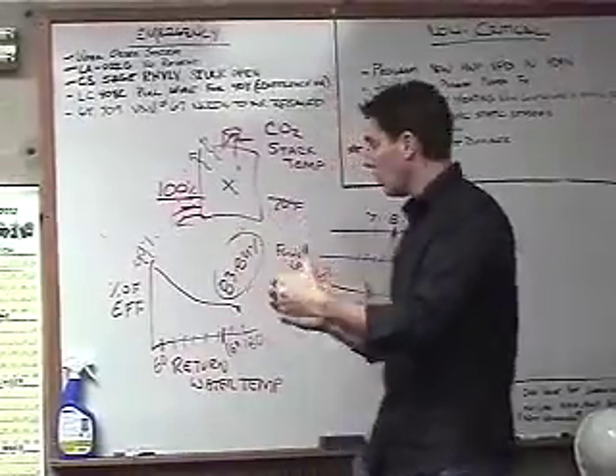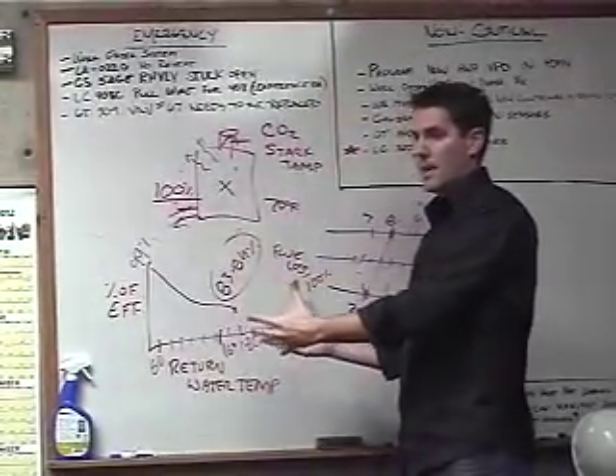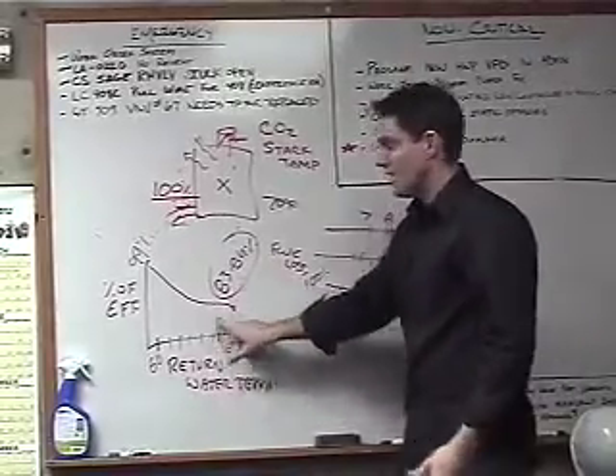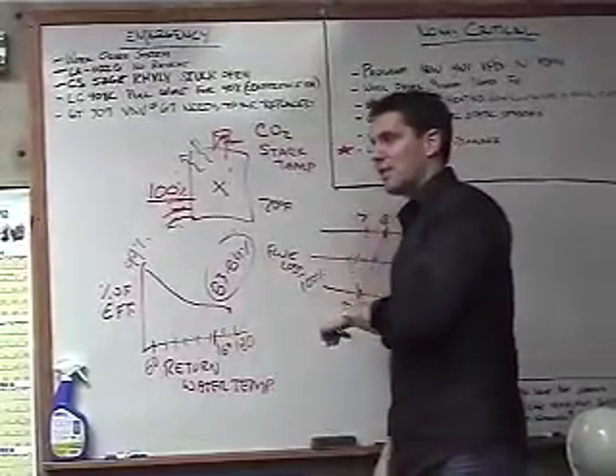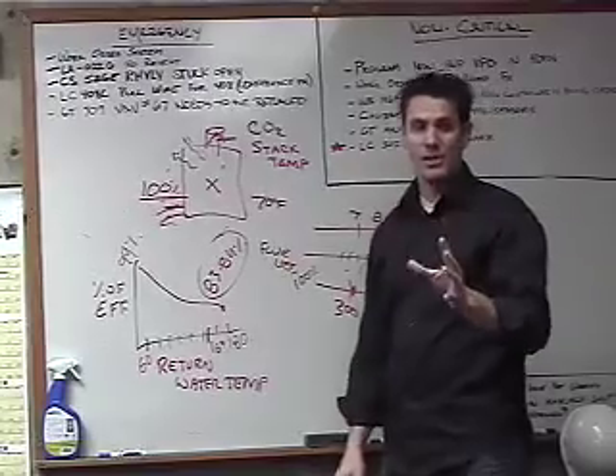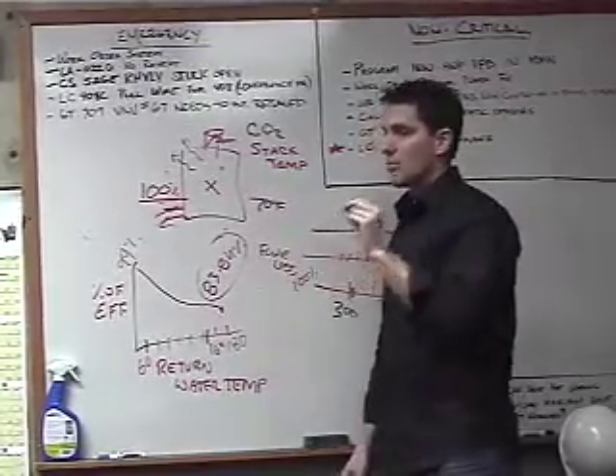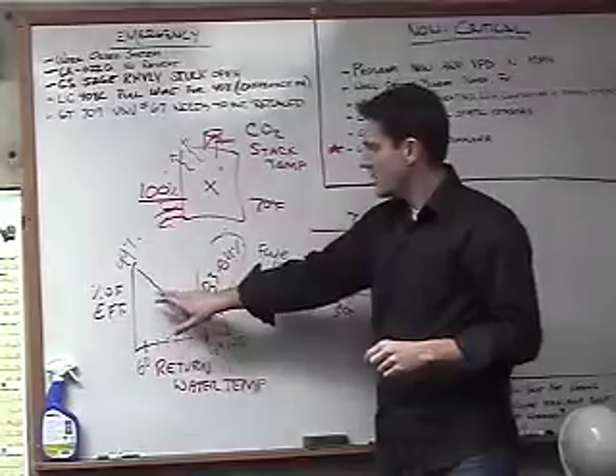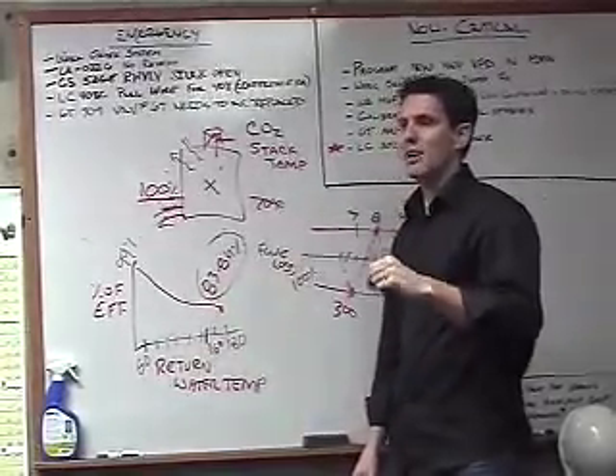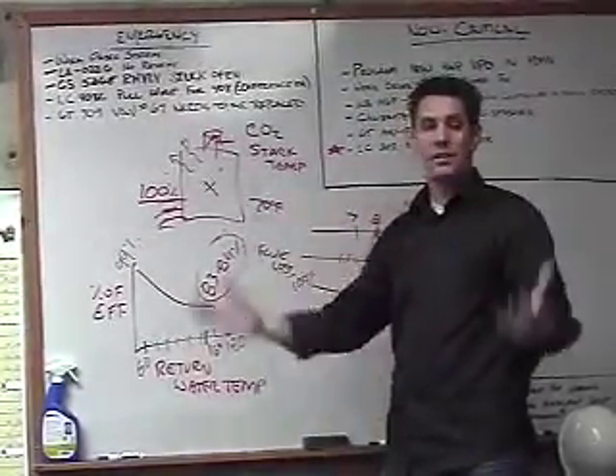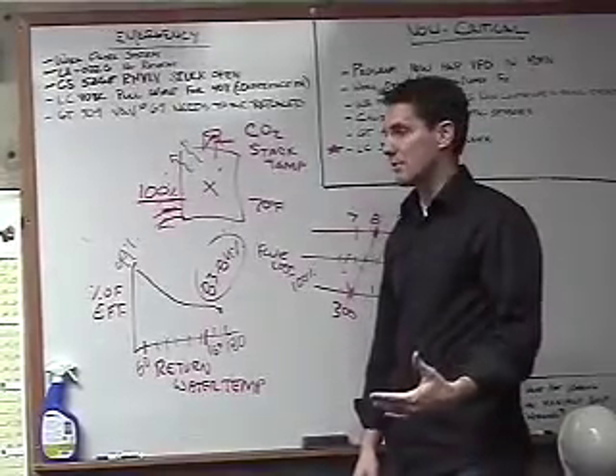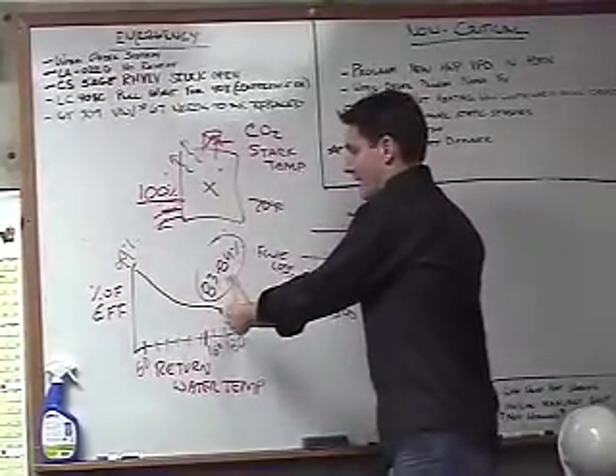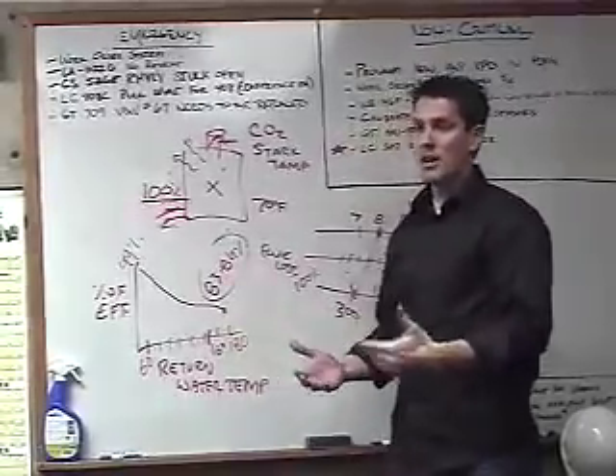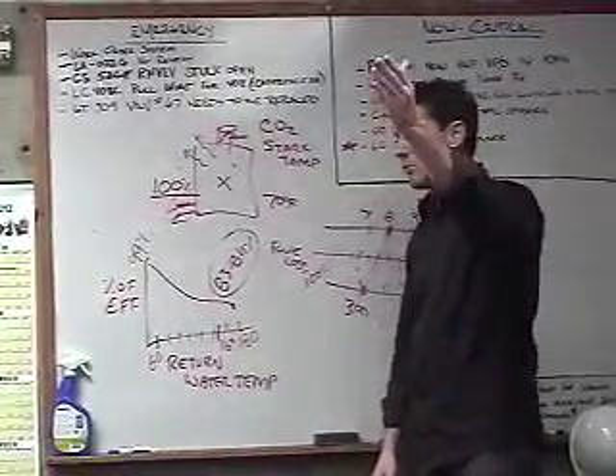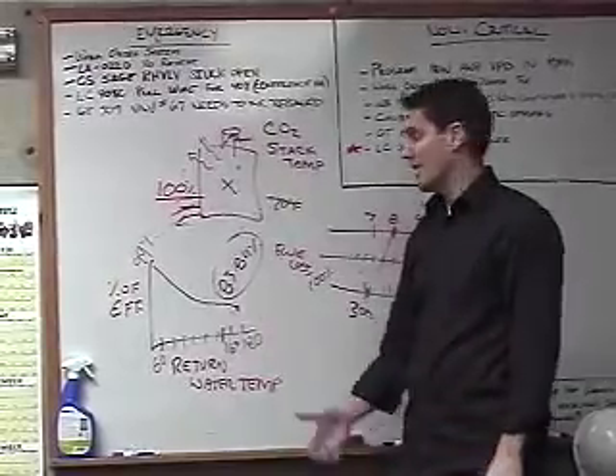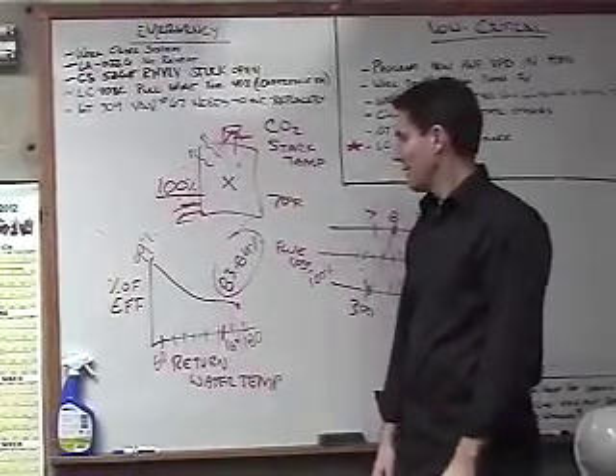So that's our number one goal with trying to create high efficient boilers. But this is what most everybody does. It's going to be your task, and I don't know everything about your system out here, to get your boiler heating system to operate as cold as you possibly can if you want high efficiency. It goes against everything you've ever thought about boilers and boiler systems. Because if I'm operating here, I might as well have just spent money on a non-condensing boiler. You've spent a whole lot more money for these boilers than you would have for a non-condensing boiler, and those boilers might even be more efficient.